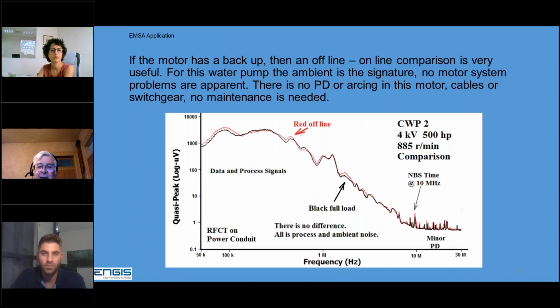If there is a backup available, this is a small power plant up in the northern part of California. We took data online and offline. The red curve is with the motor disconnected from the system. The black curve is with the motor fully loaded to 500 horsepower. And you can see the two are almost identical. So there's no difference between full load and zero load.